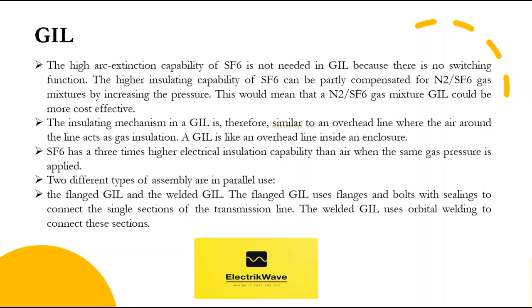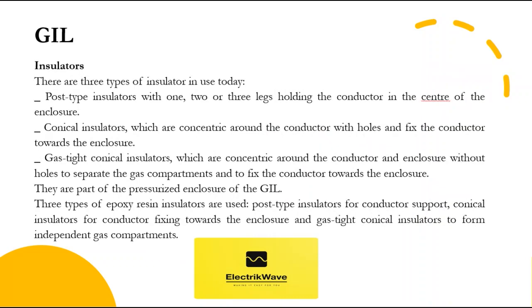SF6 has three times higher electrical insulation capability than air when the same gas pressure is applied. Two different types of assembly are in parallel use: the flanged GIL and the welded GIL. The flanged GIL uses flanges and bolts with sealings to connect the single sections; the welded GIL uses orbital welding to connect these sections. The conductor needs to be held in the center of the enclosure so that the electric field distributes equally in the concentric pipe system. Insulators are typically made of epoxy resins with filler material. There are two types of filler used today: silica and aluminum oxide. Requirements for various formulas come from features such as mechanical strength, maximum allowed temperature, electric insulation behavior, surface discharge sensitivity, and surface tracking withstandability.